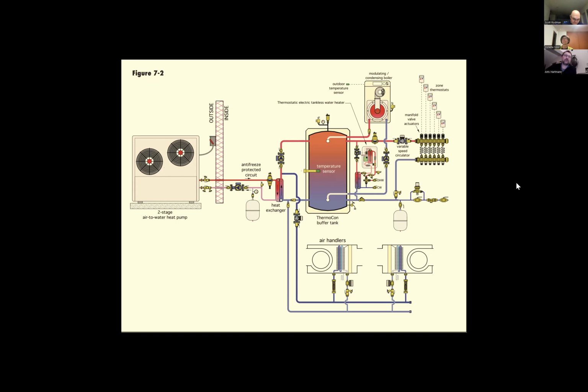I mean, the system we're using, you can do the hydronic cooling, but it requires a specific room thermostat to measure the dew point and humidity in the air, and therefore it will actually control the water temperature in the flooring to prevent the dew point and condensation on the floors. But in New England, in US weather, with that type of cooling you don't move that moisture out that much, so you still need some kind of air movement to be able to remove the moisture.